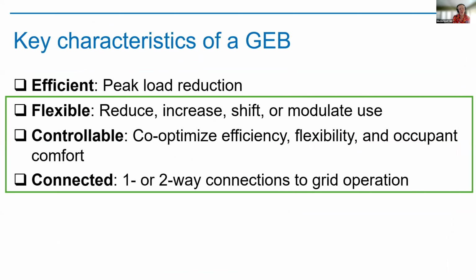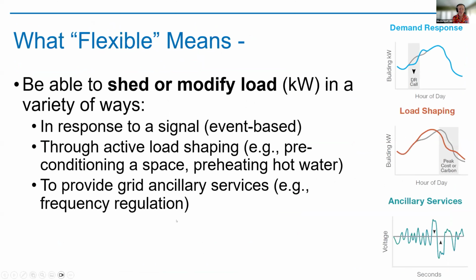If you're thinking about a grid integrated building, efficiency is one characteristic, but when we think about controls, what does that actually mean, and how can controls help? They can help the building be flexible, controllable, and connected. Functionally, flexibility means your building can shed or modify its load, either in response to a signal—like the traditional demand response signal—or through active load shaping, such as preconditioning a space in anticipation of a demand response call, or turning the building on before occupancy, letting it float overnight, and things like that.